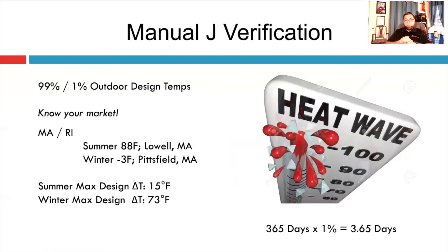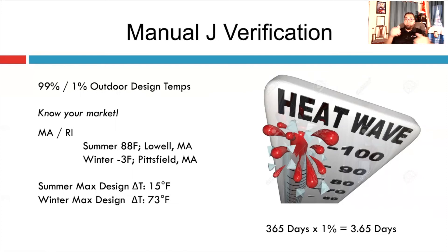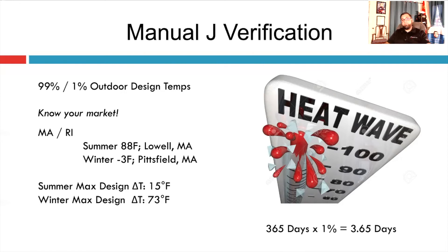Know your market. Most of you are working in the same area and should know your design temperatures. If you're in Massachusetts or Rhode Island, anything above a 15-degree delta in summer means you're oversizing the equipment. Anything more than a 73-degree delta in heating, even in Pittsfield, Mass, means you're oversizing. The highest cooling design temp is 88 in Lowell; the coldest heating temp is negative 3 in Pittsfield. Any temperatures above or below those extremes mean you're oversizing your system, and it won't meet code or rebate requirements.